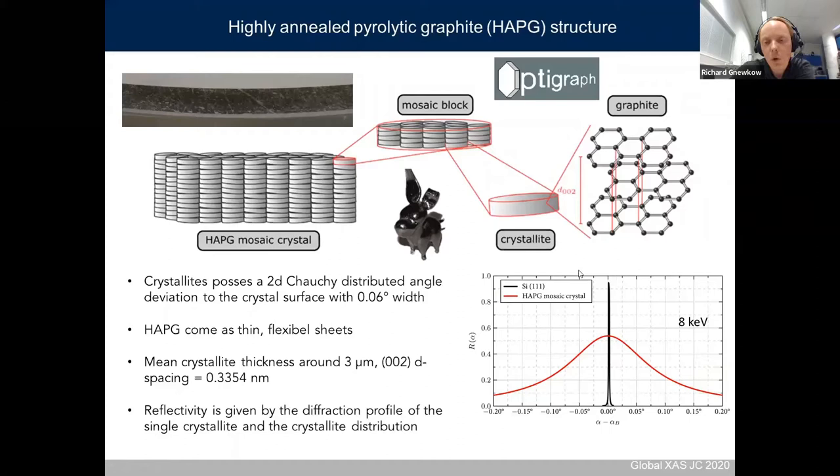Two important facts about the HAPG crystal: the mean crystallite thickness is quite small, around 3 micrometers, which normally means that the intrinsic reflection of these crystallites is broader than for perfect silicon crystals. The crystal cut 002 used for spectroscopy in first order has a d-spacing of around 0.3354 nanometers, close to silicon 111, giving a lowest measurable energy of around 2 keV, which is also the lowest energy this spectrometer can measure.